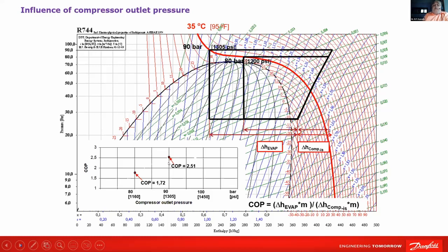now the slope is starting to come down. See, this is the 100 bar curve. There is a little bit of increase in capacity, but almost similar increase in work done. So the optimal point is somewhere peaking here.